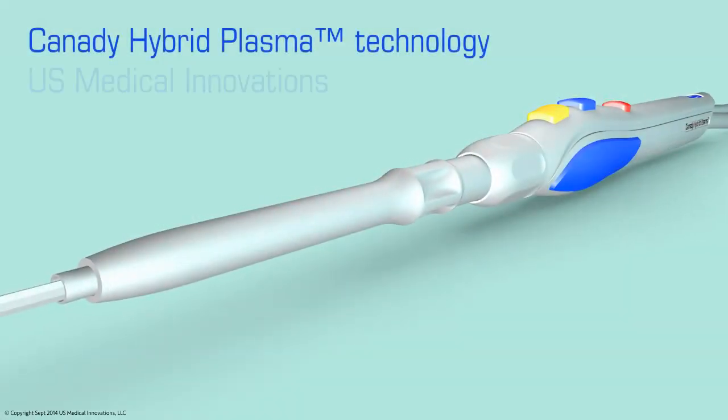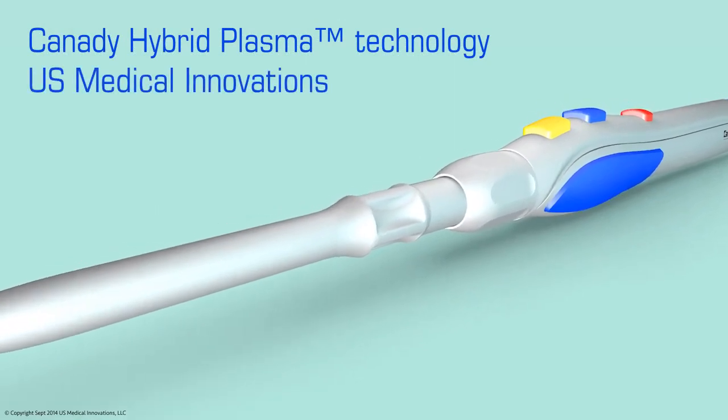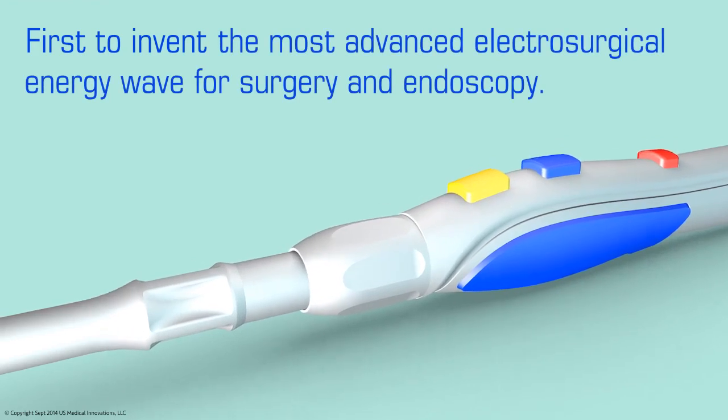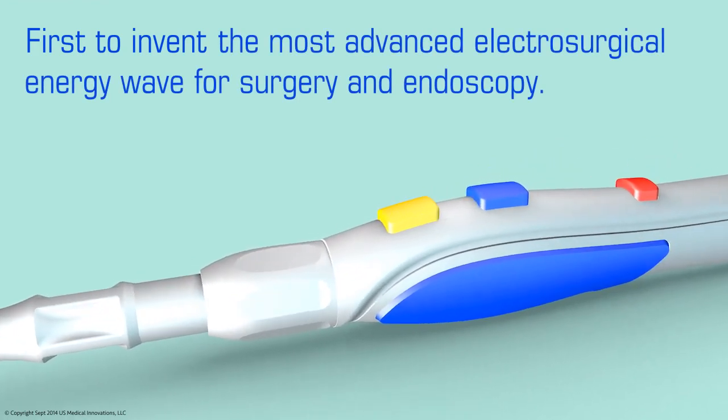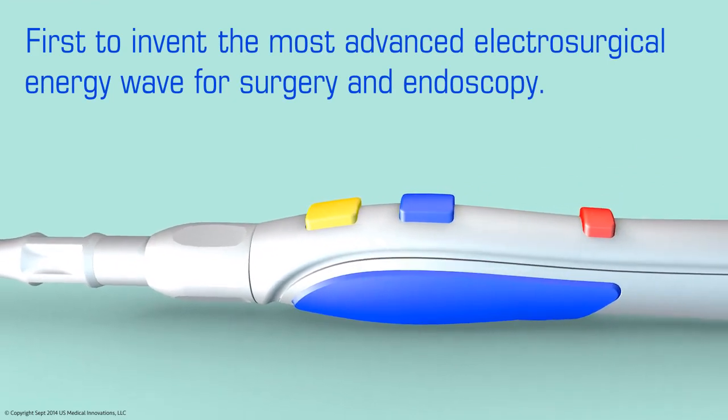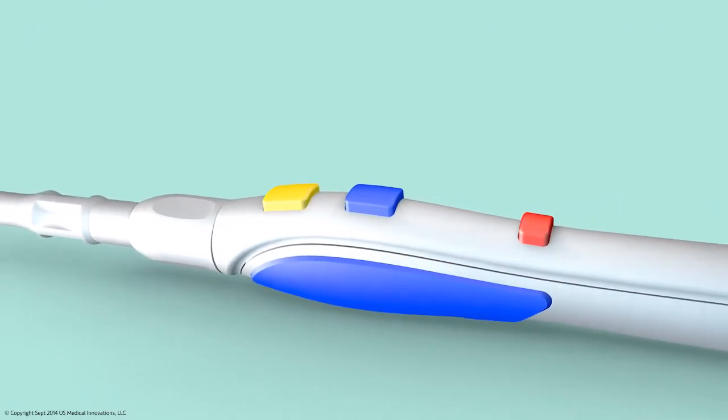Canady Hybrid Plasma Technology from US Medical Innovations is the most advanced electrosurgical energy wave developed for surgery and endoscopy today, using a microprocessed electrosurgical unit delivering a graded monopolar frequency with a plasma gas.